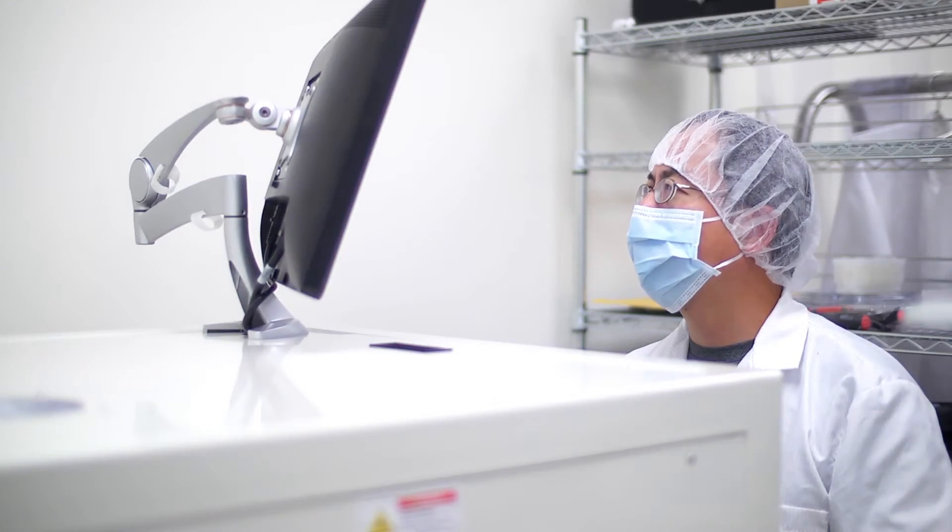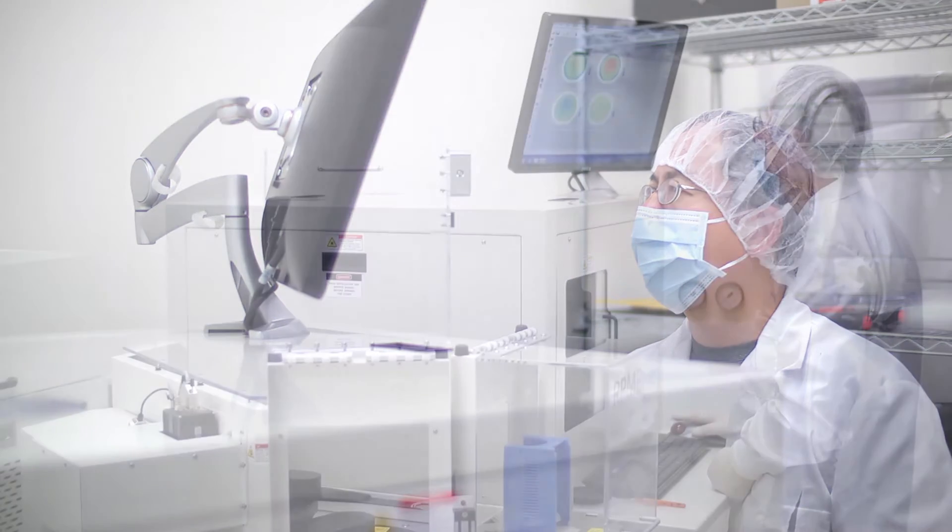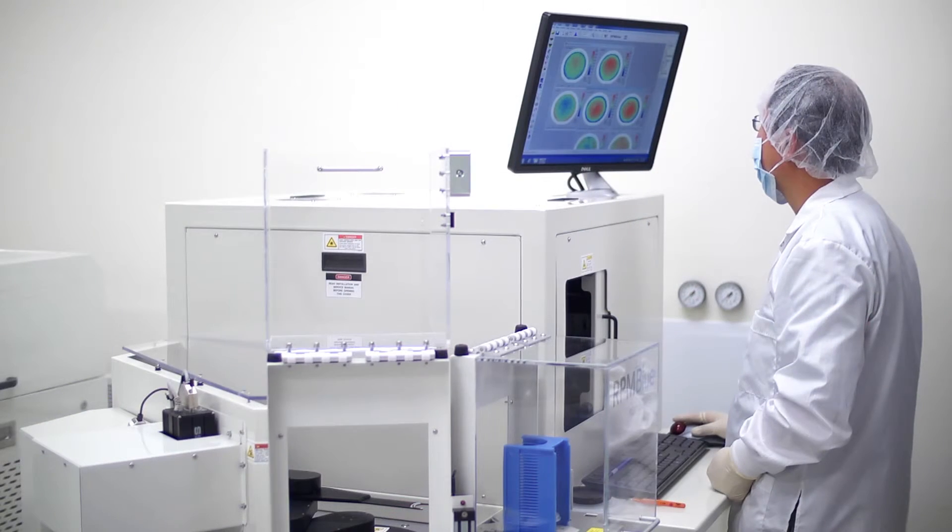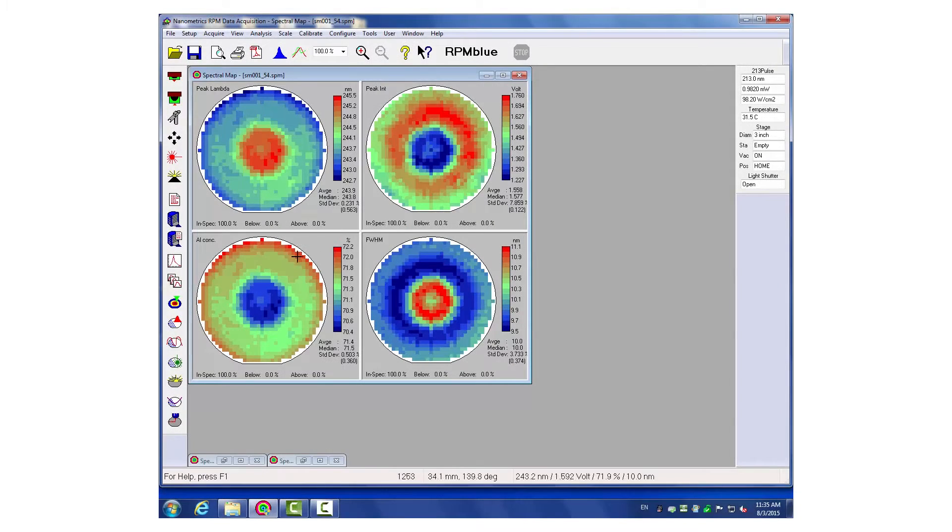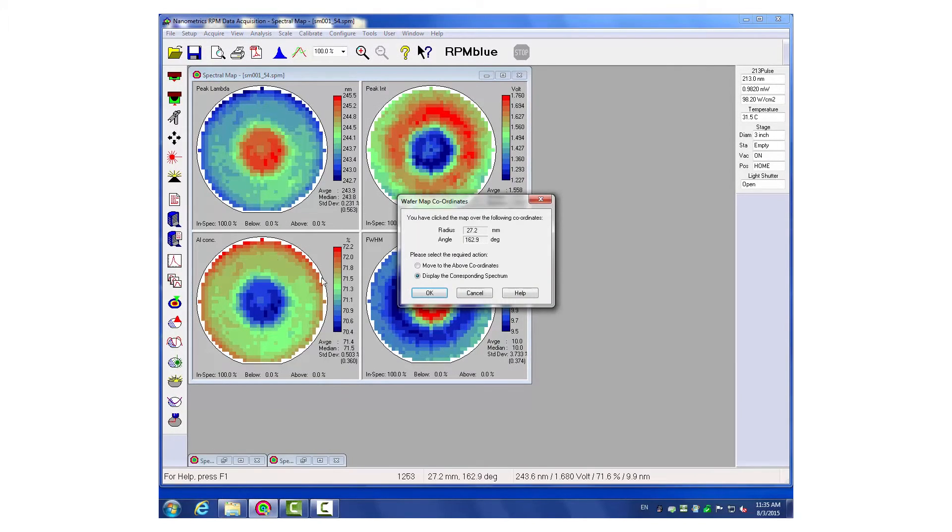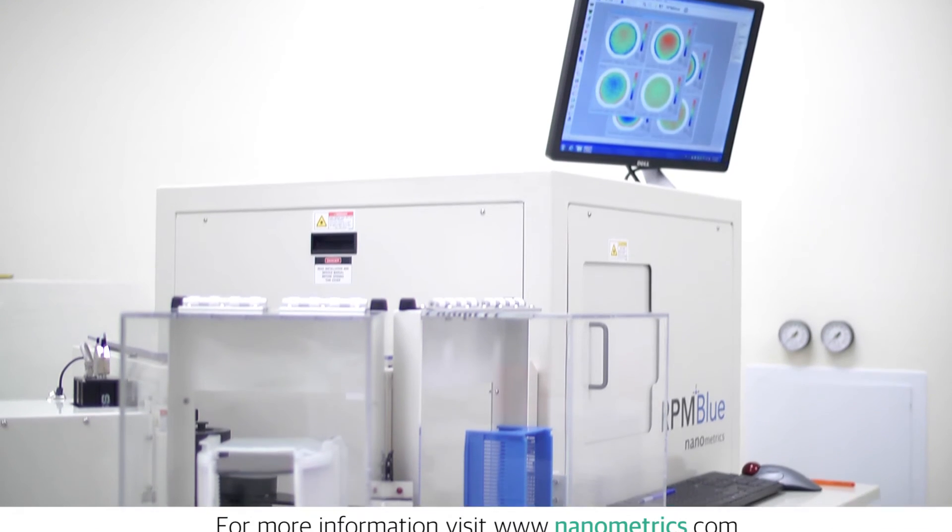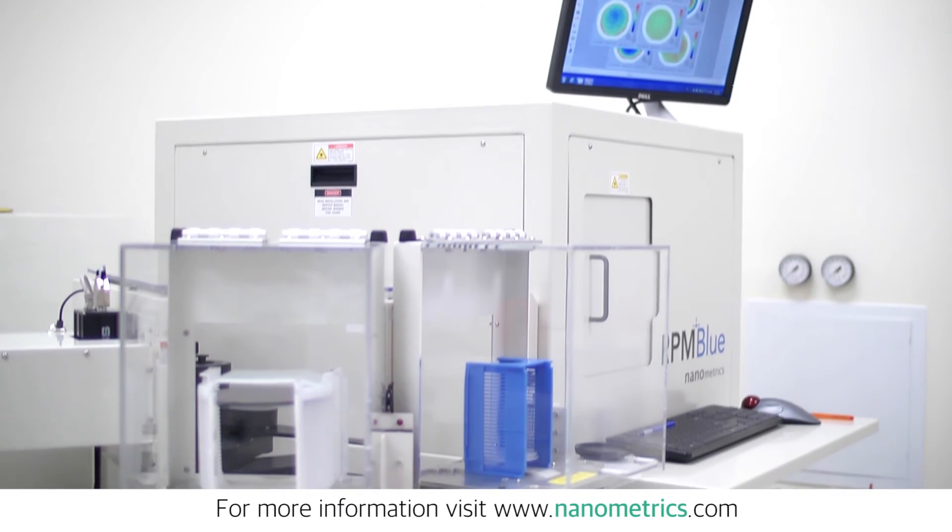Gallium nitride-based devices can be characterized using the all-new DUV option for the RPM Blue FS. With excitation lasers using 213 nanometer wavelength and specialized gratings and detectors, aluminum concentration in aluminum gallium nitride alloys can be determined up to 90% aluminum content.